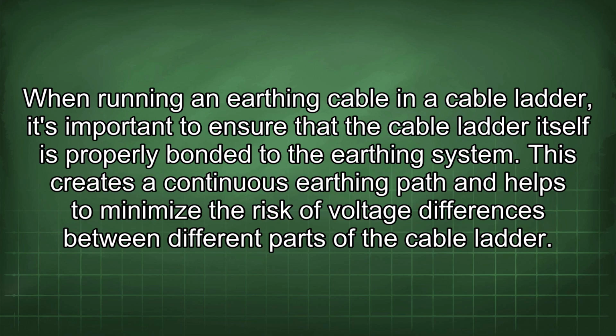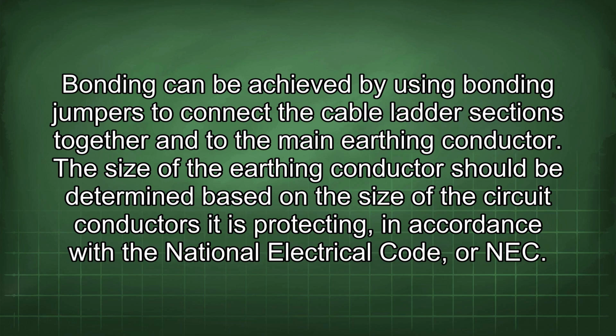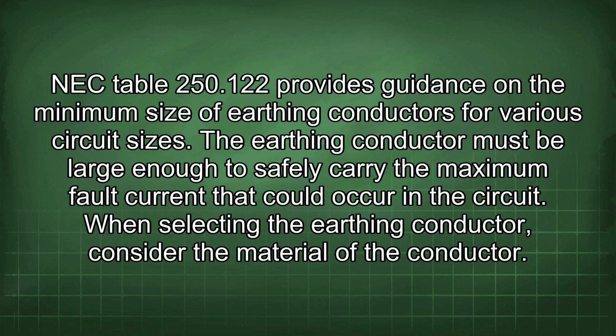This creates a continuous earthing path and helps to minimize the risk of voltage differences between different parts of the cable ladder. Bonding can be achieved by using bonding jumpers to connect the cable ladder sections together and to the main earthing conductor. The size of the earthing conductor should be determined based on the size of the circuit conductors it is protecting, in accordance with the National Electrical Code, or NEC. NEC Table 250.122 provides guidance on the minimum size of earthing conductors for various circuit sizes. The earthing conductor must be large enough to safely carry the maximum fault current that could occur in the circuit.